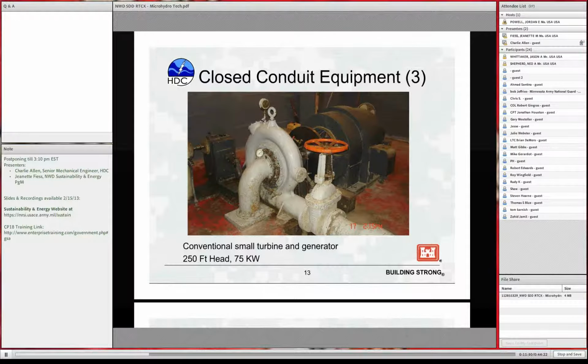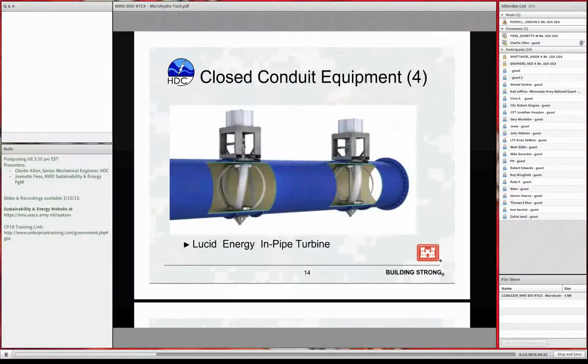This is a conventional turbine. In fact, this picture is of a 50-year-old turbine at a valve house in Afghanistan. The white device in the middle with the decreasing spiral is the turbine. The brown round device to the right, going toward the rear of the picture, is the generator. Off to the left of the turbine is a small box about 18 inches by 12 inches, which is the governor and the hydraulic pumping unit, supplying hydraulic power for the controls of the machine. This one's 75 kilowatts at about 250 feet of head, and it's truly a real turbine, just shrunk down small.